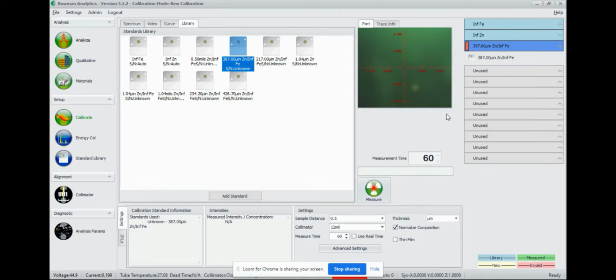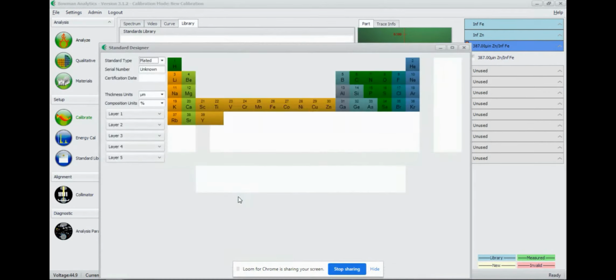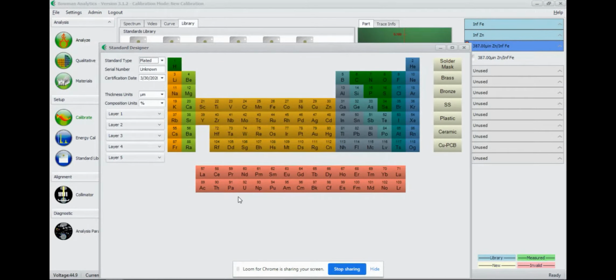Now, let's say that a standard I want is not already in the library. We can actually add standards to the library from this screen, and we're going to do that by hitting this Add Standard button. And I have a plated 1100 micro-inch zinc on steel standard. So we're going to choose plated. If it was just a foil, we're going to want to hit foil. We're plated, so we're going to hit plated. If you want to put in the serial number just so you know which one you're actually using, you can do that. This one is AEJK.